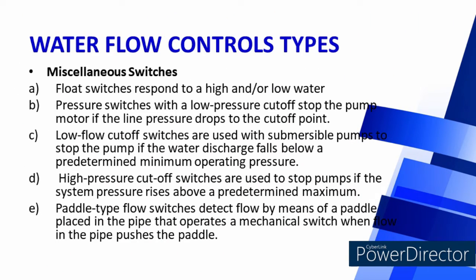Miscellaneous switches: Float switches respond to high and/or low water levels. Pressure switches with a low-pressure cutoff stop the pump motor if the line pressure drops to the cutoff point. Low flow cutoff switches are used with submersible pumps to stop the pump if water discharge falls below a predetermined minimum operating pressure. High pressure cutoff switches stop pumps if system pressure rises above a predetermined maximum. Paddle-type flow switches detect flow by means of a paddle placed in the pipe that operates a mechanical switch when flow pushes the paddle.